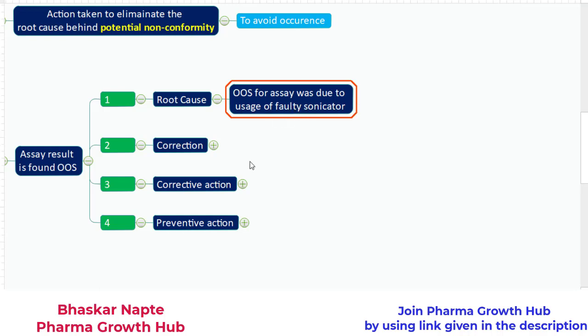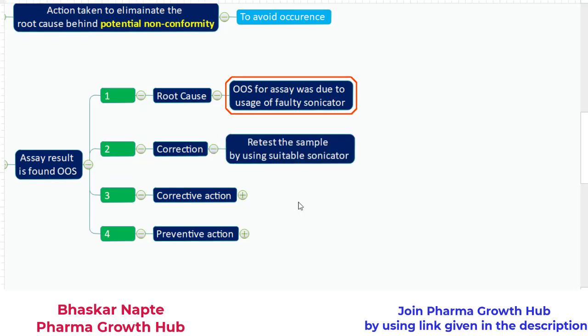So what is the correction? Correction is just to correct the non-conformity. The non-conformity here is the faulty sonicator. How you are going to correct this? Retest the sample by using a suitable sonicator — you are not going to use the faulty sonicator anymore, but a sonicator which is performing well. The extraction will happen as usual and your assay result will not be out of specification. This is the correction.